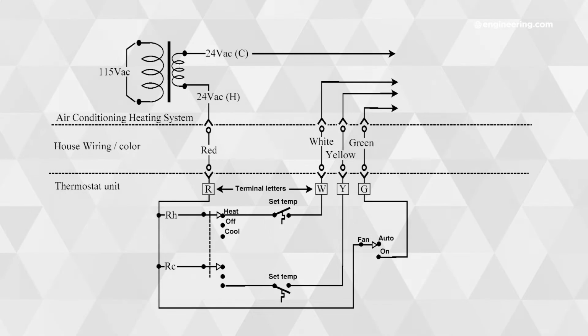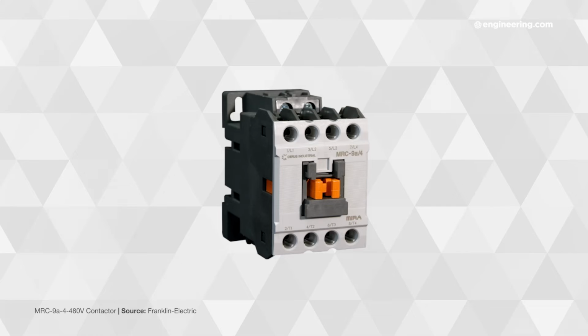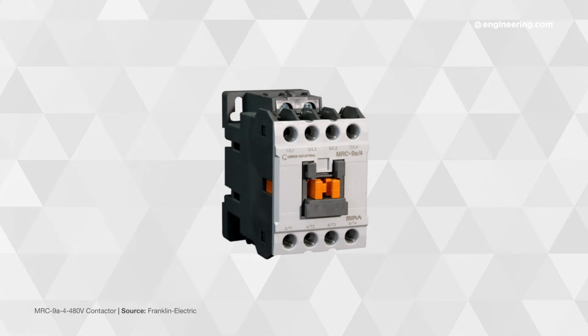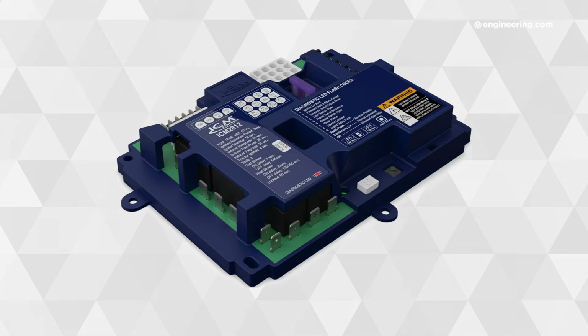This particular fuse protected a 24-volt AC circuit that energizes the coil on a single-pole double-throw contactor that controls current to an air conditioning compressor. Contactors themselves were an innovation, allowing safe, low-cost, low-voltage control currents to manage distinctly unsafe, high-voltage, high-power circuits. This 50-cent device protects an expensive control board, and just as importantly, its failure is both visible to the naked eye and testable because the blade contacts are exposed at the top of the circuit for testing.